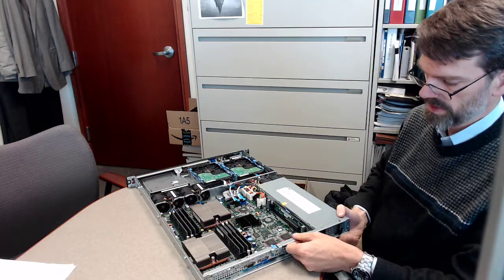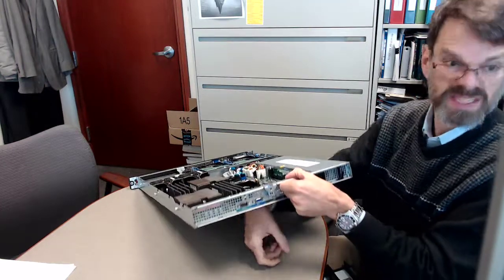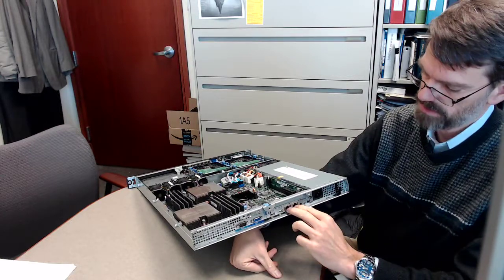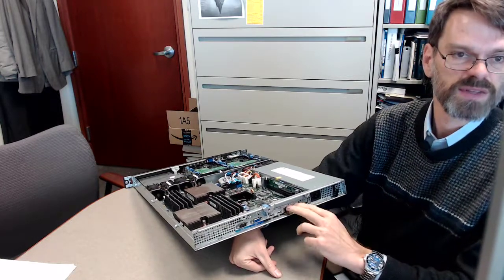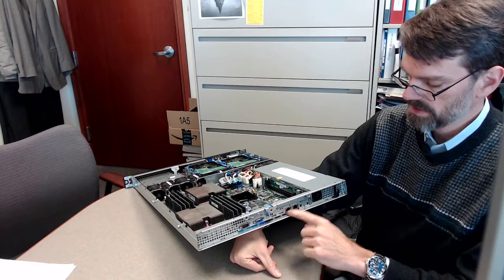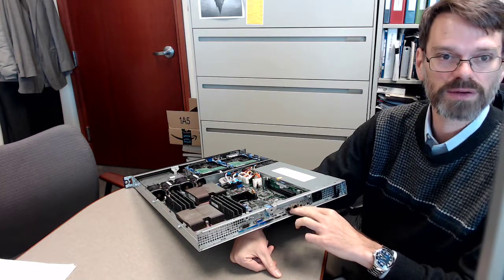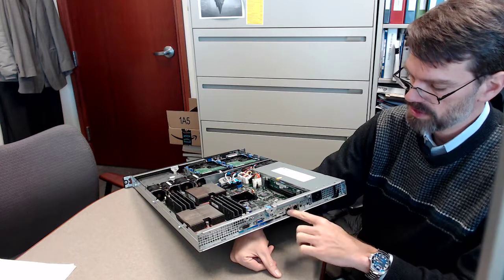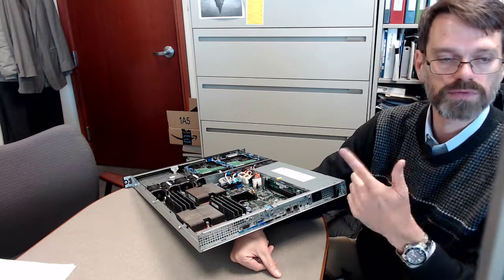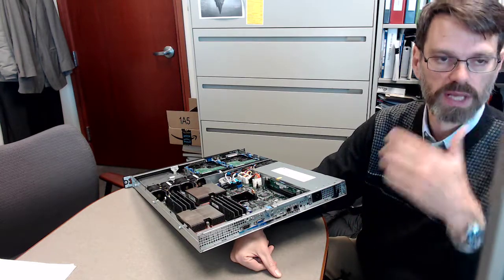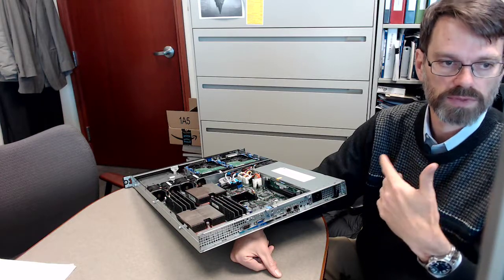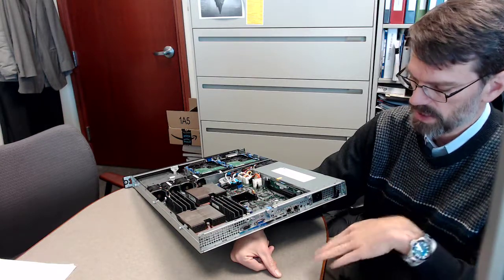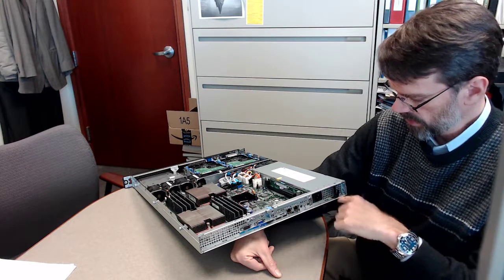But one of the things I wanted to show you here is that on the very back of this, you'll notice we have two network ports. So these are redundant. So if one fails, the other one will switch over. And in fact, when we had this installed in the data center, each network cable would go to a different switch. So if there's something wrong with the cable or if there's something wrong with the switch, we tried to build as much redundancy in as we could.